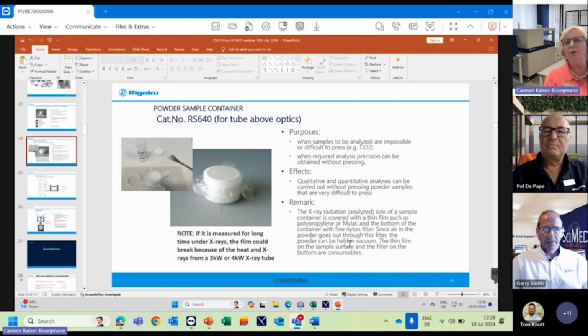So we have what we call a powder sample container, and it looks like this. It has a nylon filter. You can place your loose powder in here with a film on top, and place the snap-on ring. It's designed for you to carry out a measurement with very high heat, like a 3 kilowatt or even a 4 kilowatt if you go for the bigger instrument. And it's really easy to measure this in vacuum, since it's designed for vacuum measurements.